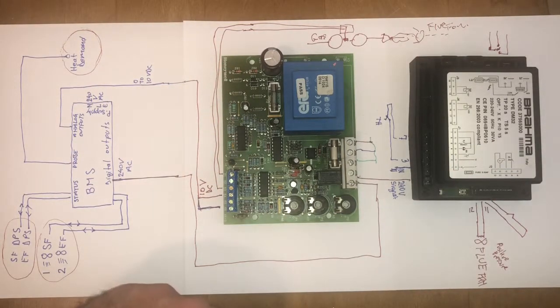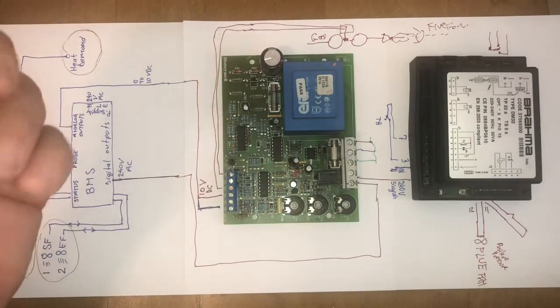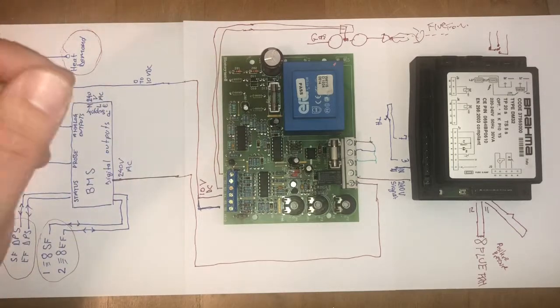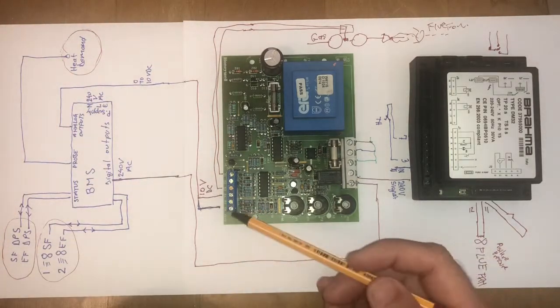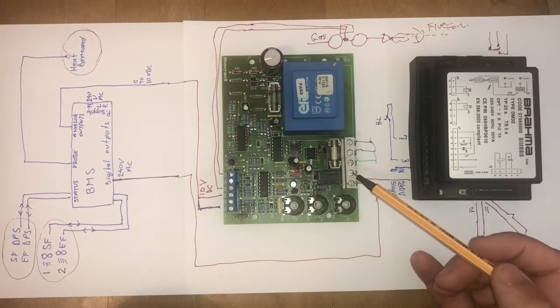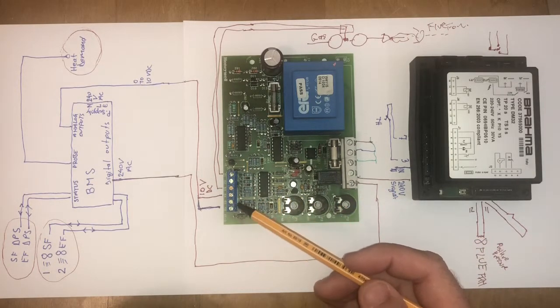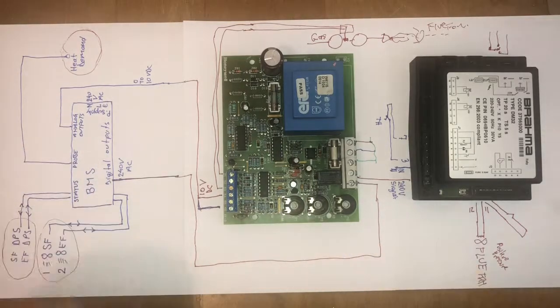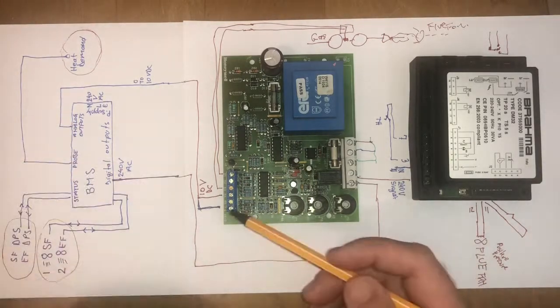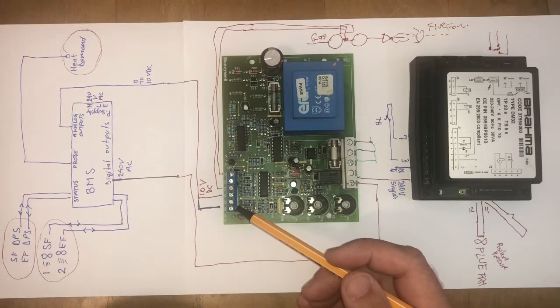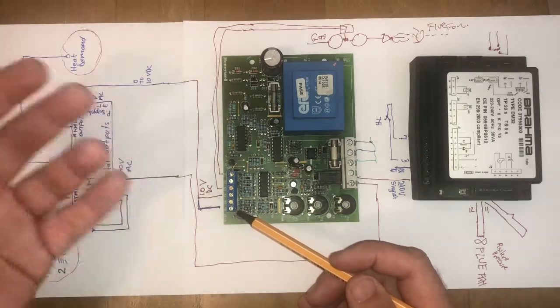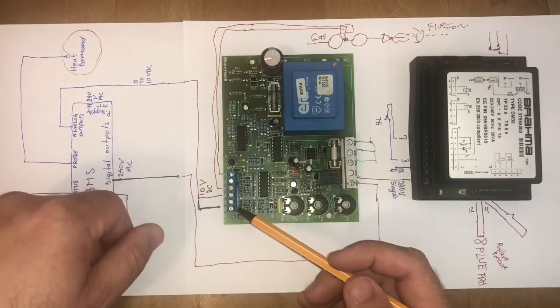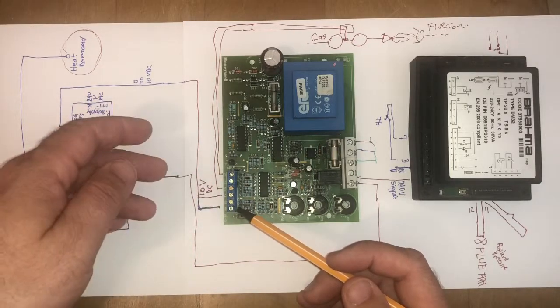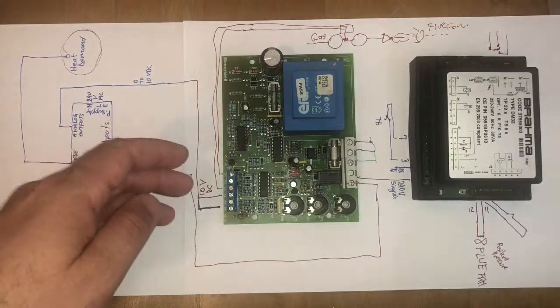If you bypass this straight in here, you might have either high flame or low flame when you do the combustion analysis. So for you to have a proper design, I suggest that you make sure you have 240 volts right here, and then you have 10 volts here. And if not, you have to contact the people who control the building management control. If you're smart enough, you can use a 9 volt battery to apply power here, and then if you have a potentiometer to drop down the power to 5 volts, then you can lower the flame.